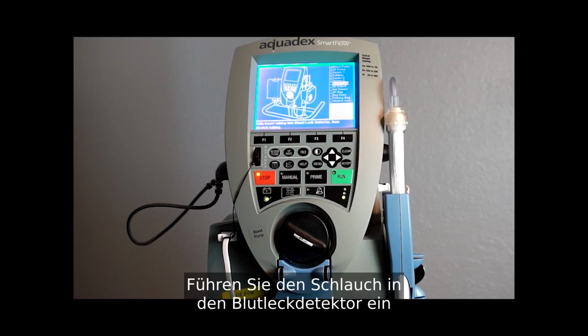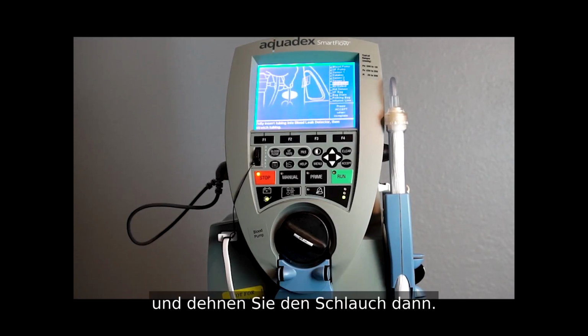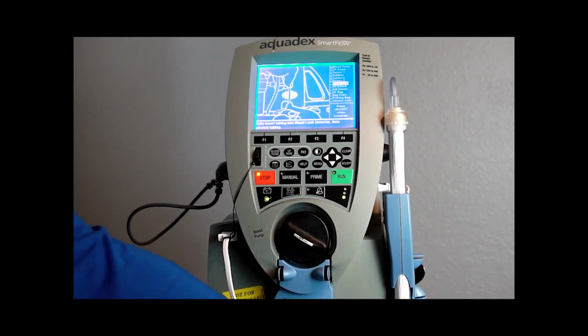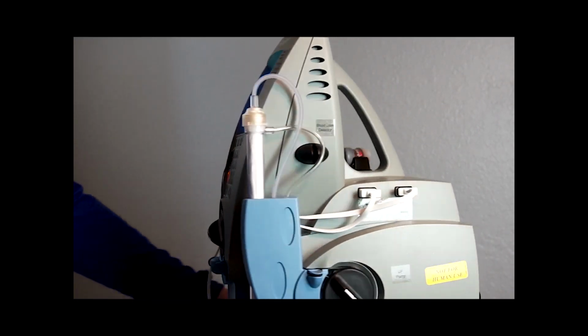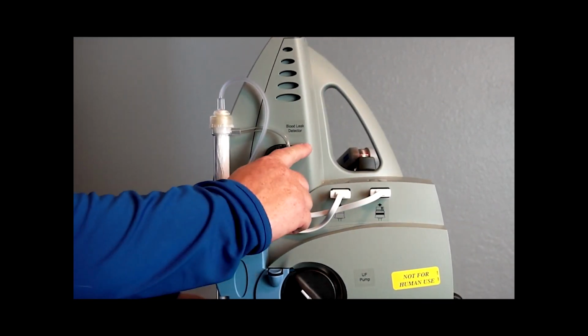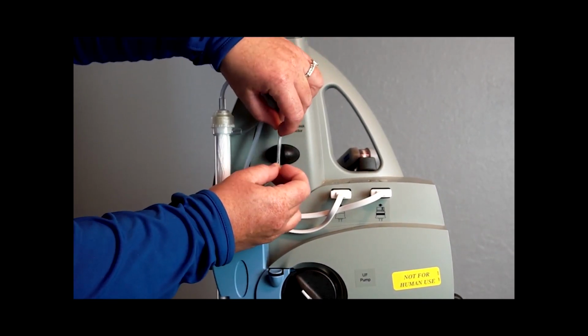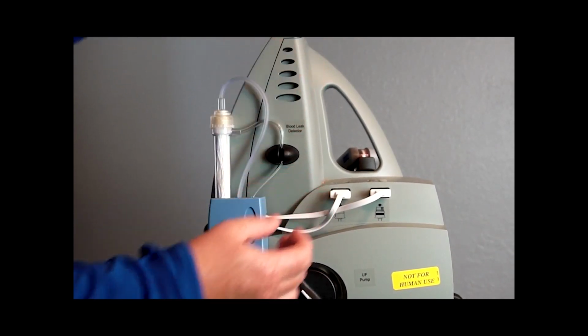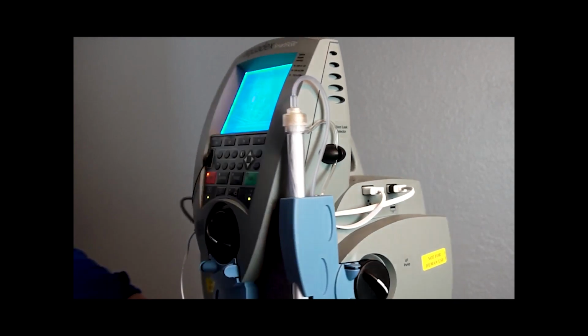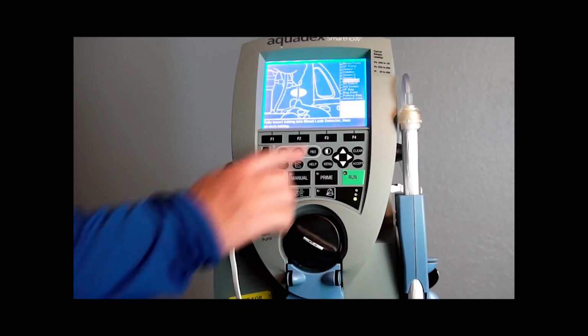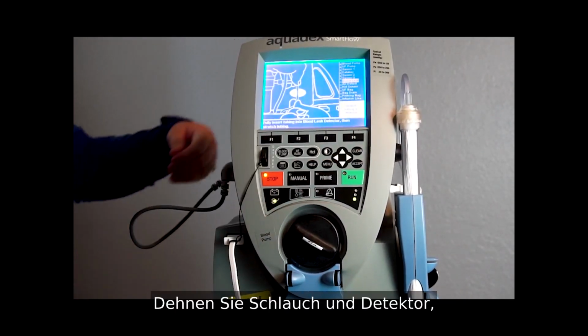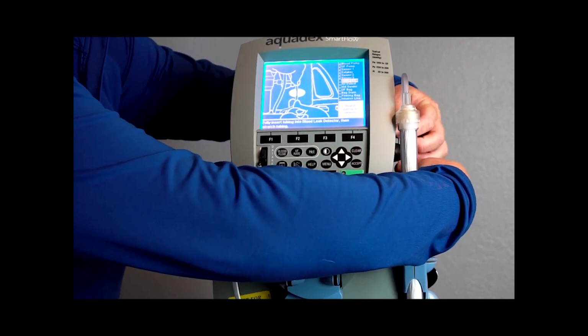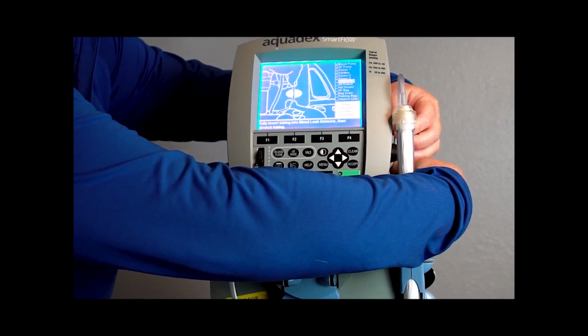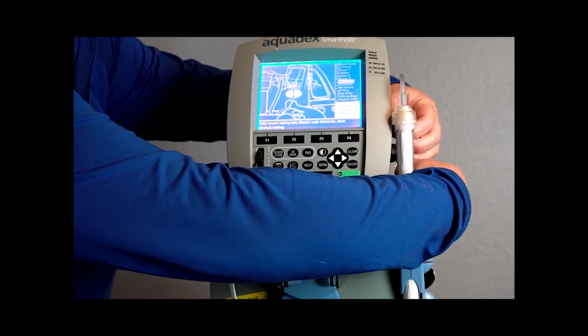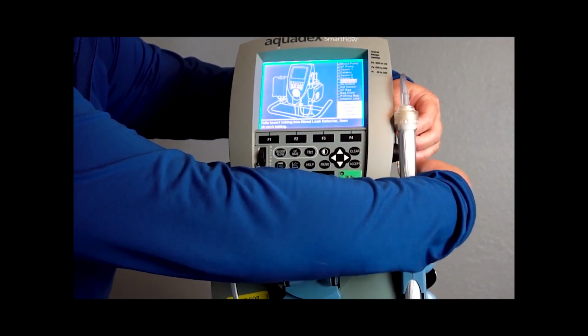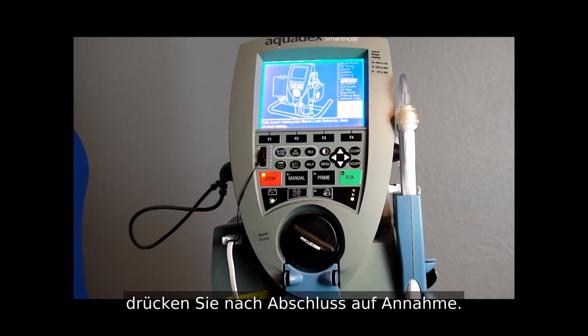Insert tubing into the blood leak detector, then stretch tubing. Stretch tubing in detector. Press Accept when complete.